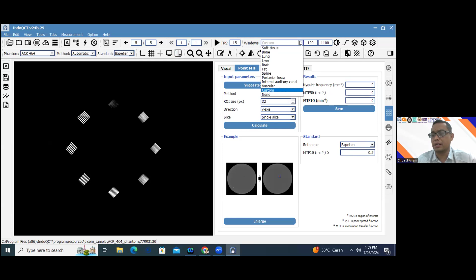For the point MTF, we can also use the automatic or manual method. The manual method means that this is the ROI, and we locate the ROI on the object like this. After the ROI covers the object, we calculate like this. Then we obtain our ROI, and this one is our PSF, the point spread function in one dimension. This one is the Fourier transformation of the PSF, and this curve is called the MTF, modulation transfer function. The software will show you the 10% MTF; in this example it is around 0.6, and the exact value you can see here.